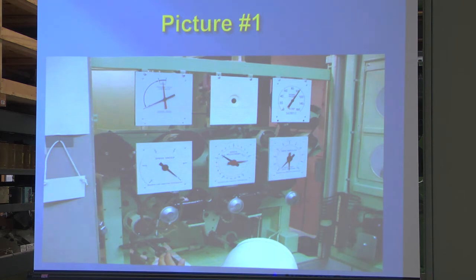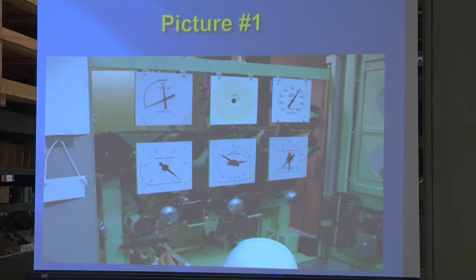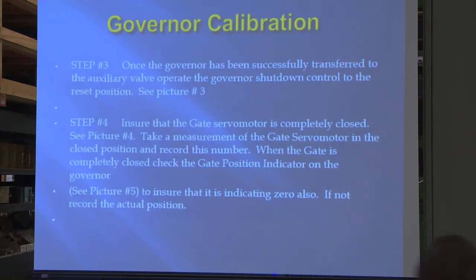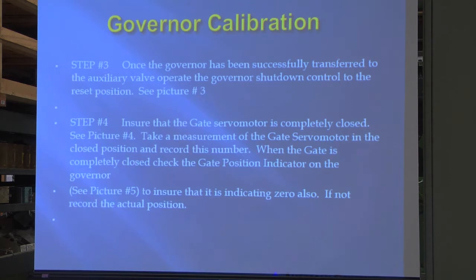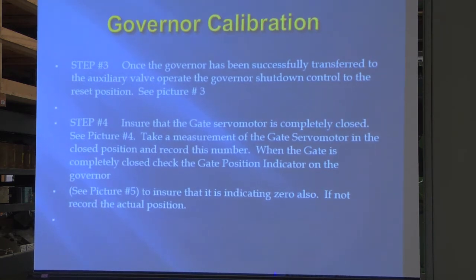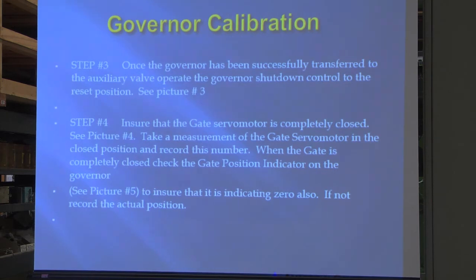And this is showing a picture of the gauges and everything. This is the Type B cabinet, probably just like you got, okay? And you can see the little stacks of limit switches will be in here, huh? Usually running out this way for your cams. Showing picture 2 is all right. Step 3, once the governor's been successfully transferred to the auxiliary valve, operate the governor shutdown control to the reset position. See picture 3. This picture just doesn't do me any justice at all here. But if you go and read it again, shutdown to the reset position.